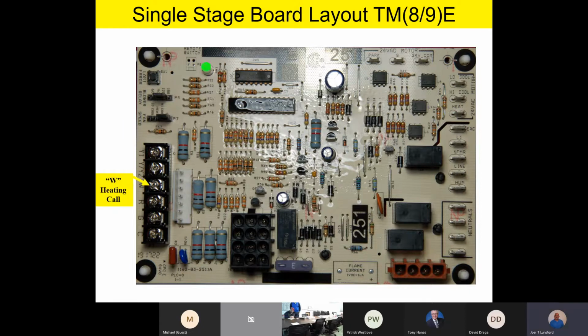W will be our heating call. Now remember, team, on a single stage board like this, you're just going to have the single W terminal. On a 2-stage board, you'd have a W1 and a W2, but because this is single stage heating, we're just going to have a single W terminal for our heating input from the thermostat. R will be our 24-volt hot. That's pretty standard in the industry as far as low voltage wiring.